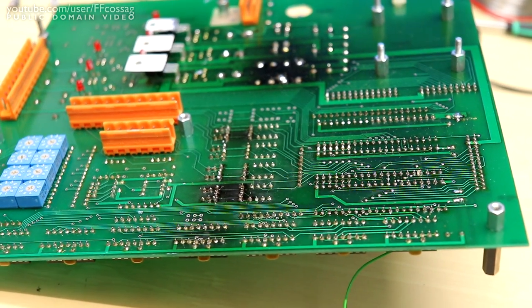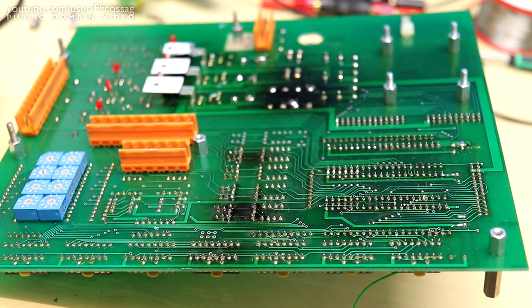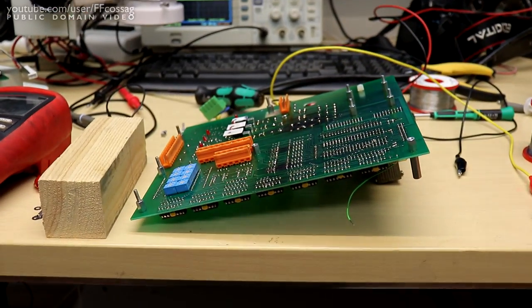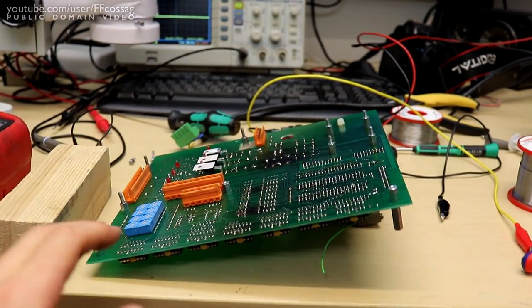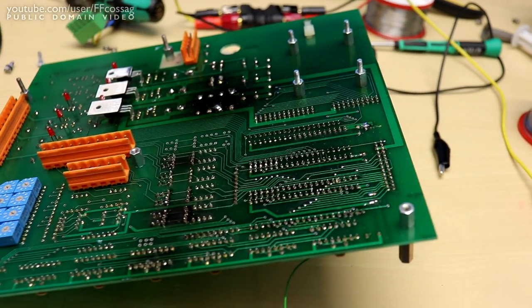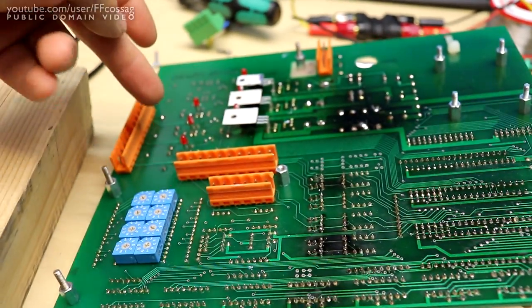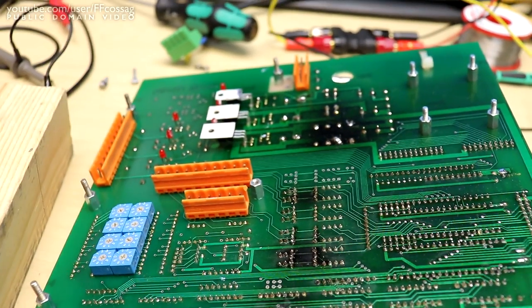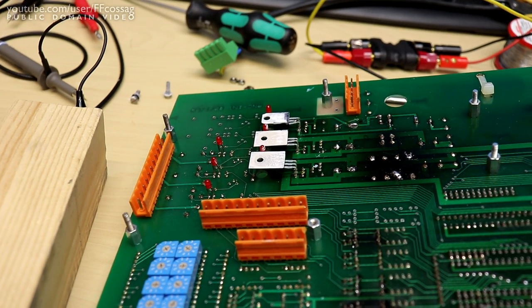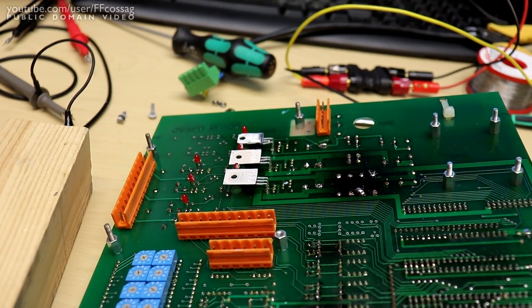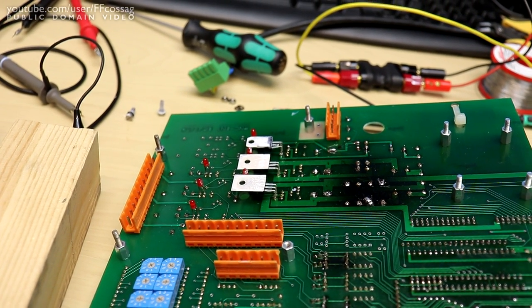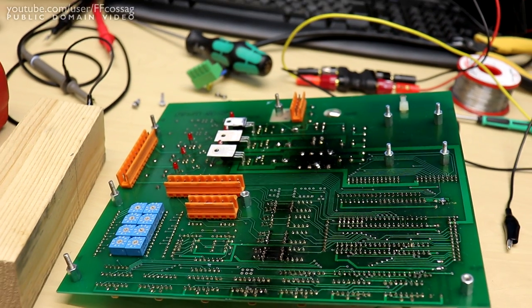But while that does look horrible, I have actually tested every single optic coupler input and they all work fine. So that's not our issue. So I spent just a few hours just redoing bunch of solder joints. All the joints for these 68000 series interface ICs have been redone. I've checked, there are three relays which are relay outputs from this board. I've taken out the relays, tested those, they're fine. That's also a common issue in industrial gear - relays that just don't see enough loading to last, essentially. They never see a spark, so they oxidize over time. But sadly, no issues like that.